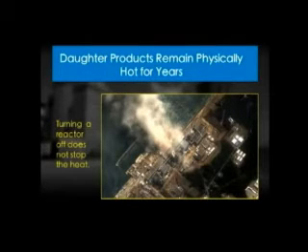Fukushima 1 is slightly older, and if you look at it from left to right, it's Fukushima 1, 2, 3, and 4. And this picture was taken before Unit 4 blew up, but while Unit 4 was on fire. So the 2 smoldering buildings there are Unit 3 and Unit 4. Their containments are designed to contain the radiation. I think we can all agree it didn't work. It didn't work not just once, not just twice. It didn't work 3 times out of the 3 times it was tried. So this is the first real test of a boiling water reactor containment, and it went 0 for 3.